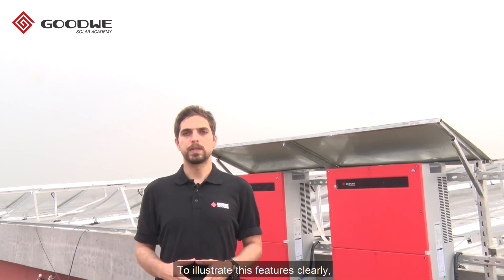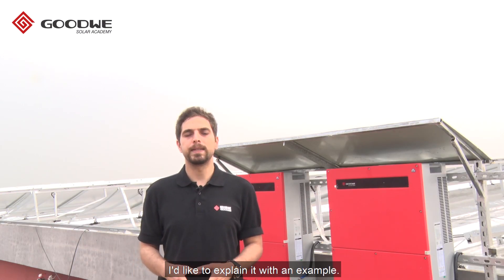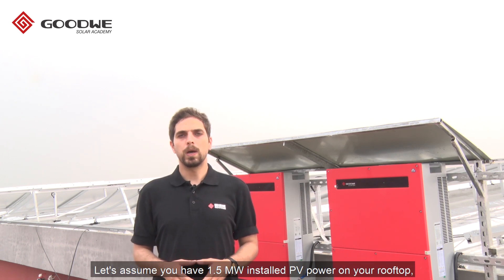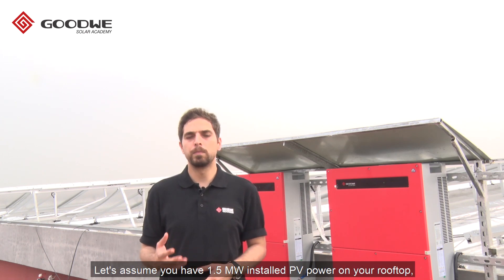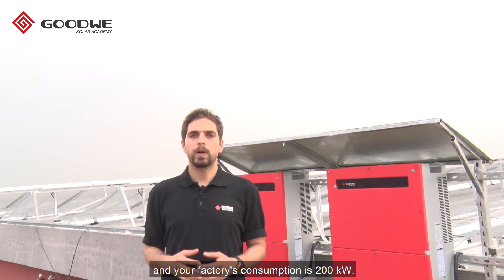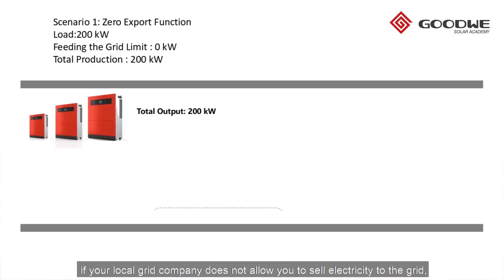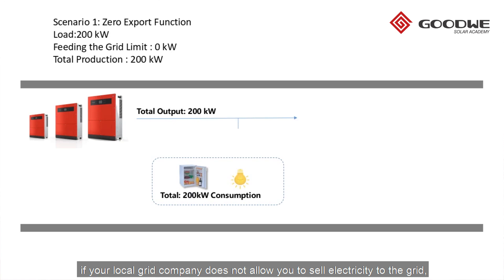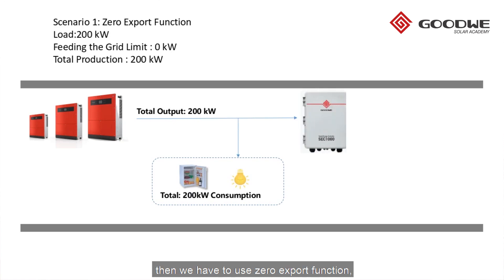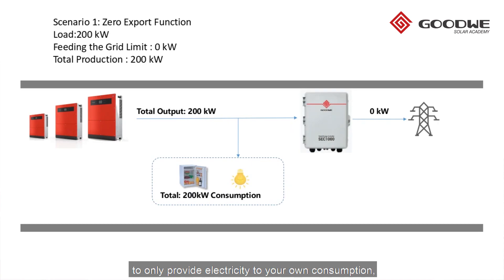To illustrate these features clearly, let me explain with an example. Let's assume you have 1.5 megawatt installed PV power on your rooftop and your factory's consumption is 200 kilowatt. In the first scenario, if your local grid company does not allow you to sell electricity to the grid, then we have to use the zero export function. The inverters will reduce production to 200 kilowatt to only provide electricity for your own consumption but won't feed the grid.